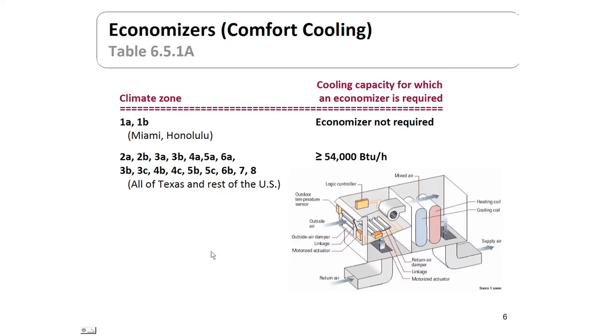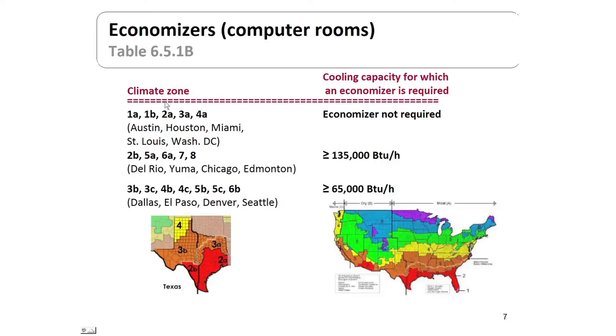Here is an illustration of the economizer cycle type of cooling, showing where it is required and where it is not. It is not required at all in climate zones 1A and 1B — that only includes Miami and Honolulu. The areas where it could be required include all of Texas and the rest of the United States. These climate zones do require economizer cooling if your system is greater than 54,000 BTUs per hour. For computer rooms, the economizer requirement is less stringent and is exempted in climate zones 1A, 1B, 2A, 3A, and 4A — which includes Austin and Houston in the state of Texas.